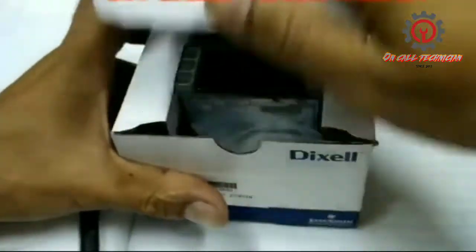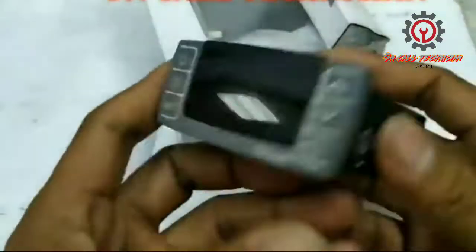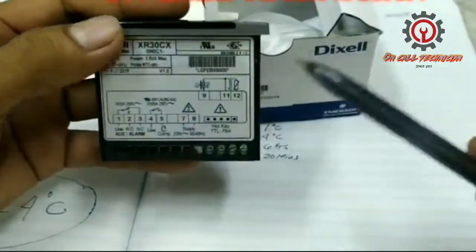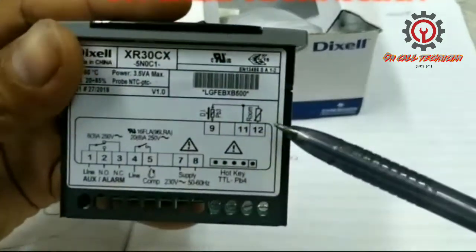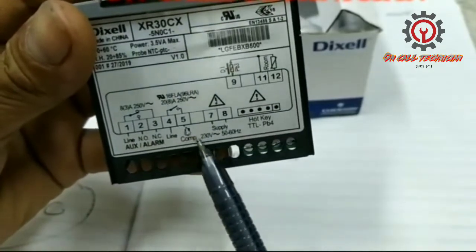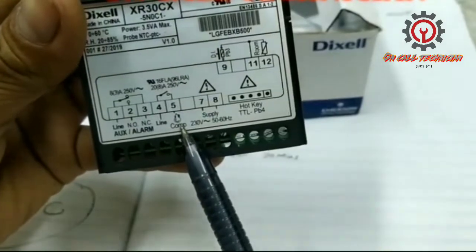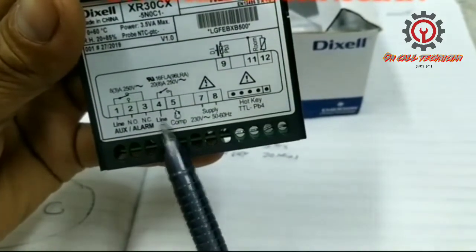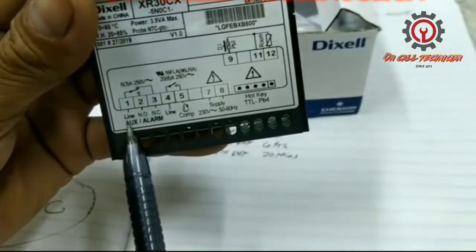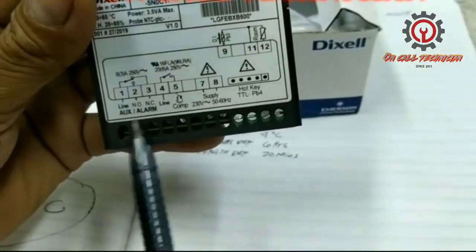Here is what it looks like inside. This is our Dixell XR30CX. Terminals 11 and 12 are for the probe sensor. Terminal one is line, and terminals two through eight — seven and eight are our supply. Terminal number five is our compressor, while four is line together with number one. Terminal two is normally open and terminal three is normally closed.